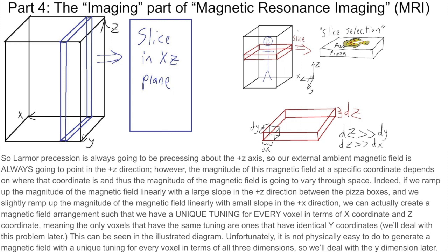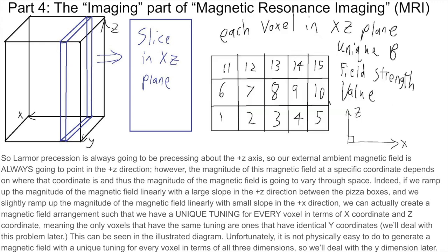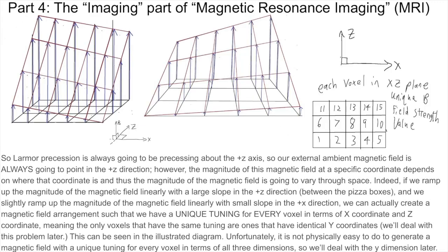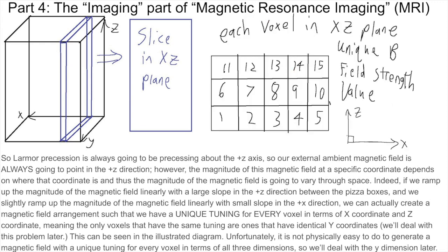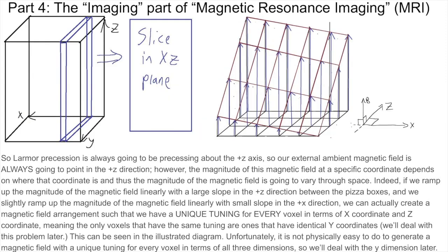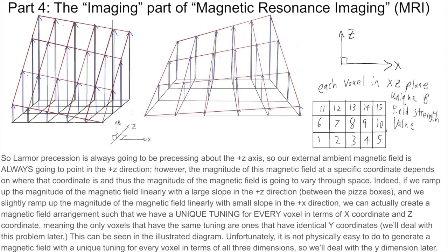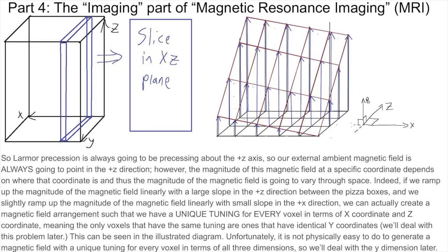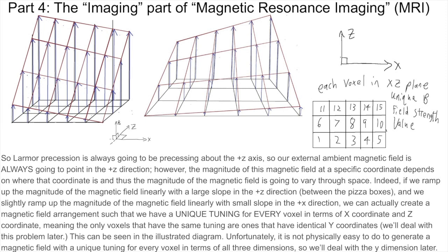However, the magnitude of this magnetic field at a specific coordinate depends on where that coordinate is in three-dimensional space, and thus the magnitude of the magnetic field is going to vary through three-dimensional space. If we ramp up the magnitude of the magnetic field linearly with a large slope in the plus Z direction between the pizza boxes, and slightly ramp up the magnitude linearly with a small slope in the plus X direction, we can create a magnetic field arrangement such that we have a unique tuning for every voxel in terms of X coordinate and Z coordinate — meaning the only voxels that have the same tuning are ones that have identical Y coordinates. We'll deal with this problem later.